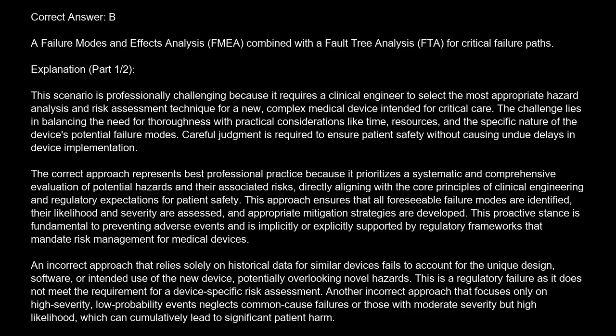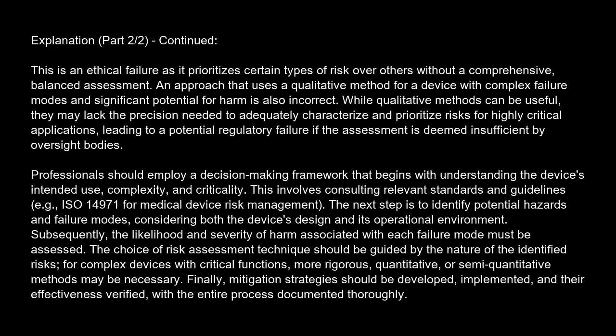Another incorrect approach that focuses only on high-severity, low-probability events neglects common cause failures, or those with moderate severity but high likelihood, which can cumulatively lead to significant patient harm. This is an ethical failure, as it prioritizes certain types of risk over others without a comprehensive, balanced assessment.